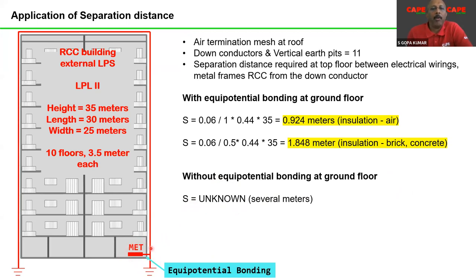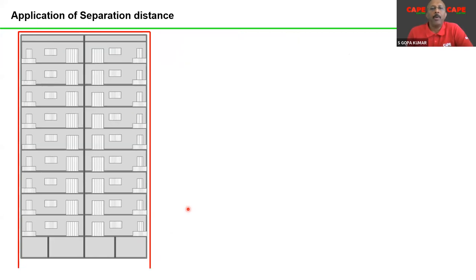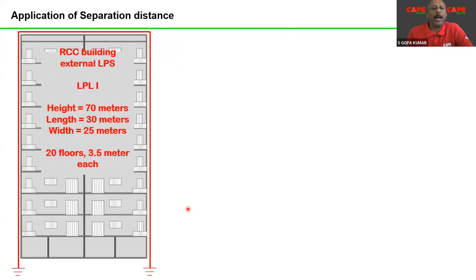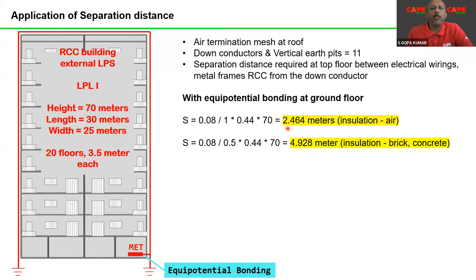In India, unfortunately, in a lot of buildings the equipotential bonding does not exist. Under that condition, please note that the separation distance would be very, very high. Practically, what can happen is there can be flashover at several points of the building. Now, I am making the same calculation for a building of height 70 meters, lightning protection level 1, a 20-floor building with 3.5 meters each, with equipotential bonding. Under that condition, the separation distances are 2.64 meters in air and 4.92, or about 5 meters, in brick.